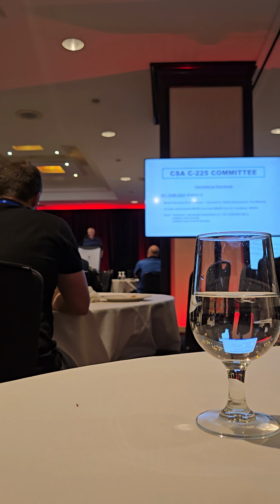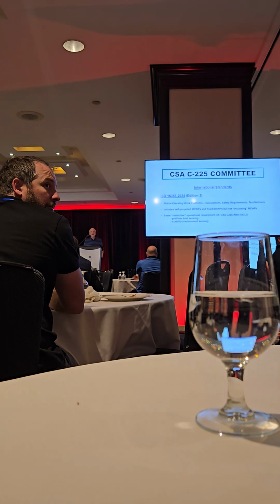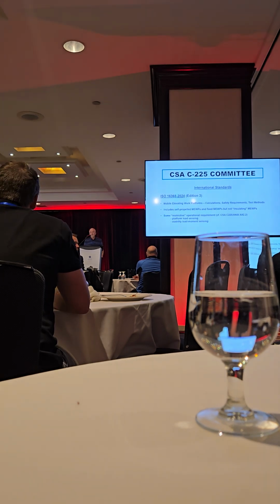So if we're going to try to adopt some of that too, load sensing was specifically not recommended in IEC 61057, because live line units have to work in a varying field intensity surrounding those live lines, and the sensors usually used for load sensing aren't immune to that field intensity. It can vary a lot, especially when you're bonding on and off a line, with huge varying charging currents and field effects coming into the basket.